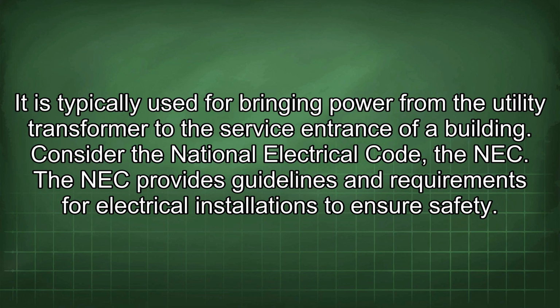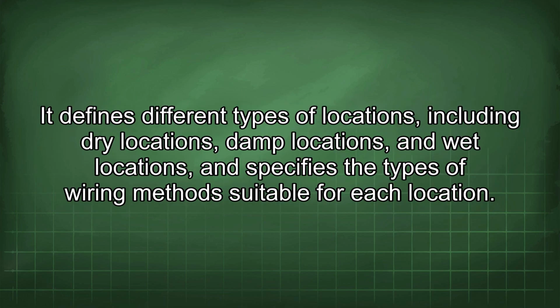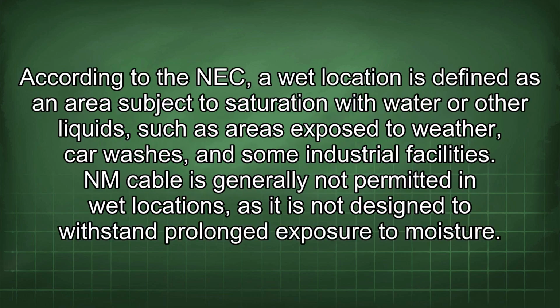Consider the National Electrical Code, the NEC. The NEC provides guidelines and requirements for electrical installations to ensure safety. It defines different types of locations, including dry locations, damp locations, and wet locations, and specifies the types of wiring methods suitable for each location. According to the NEC, a wet location is defined as an area subject to saturation with water or other liquids, such as areas exposed to weather, car washes, and some industrial facilities. NM cable is generally not permitted in wet locations, as it is not designed to withstand prolonged exposure to moisture.